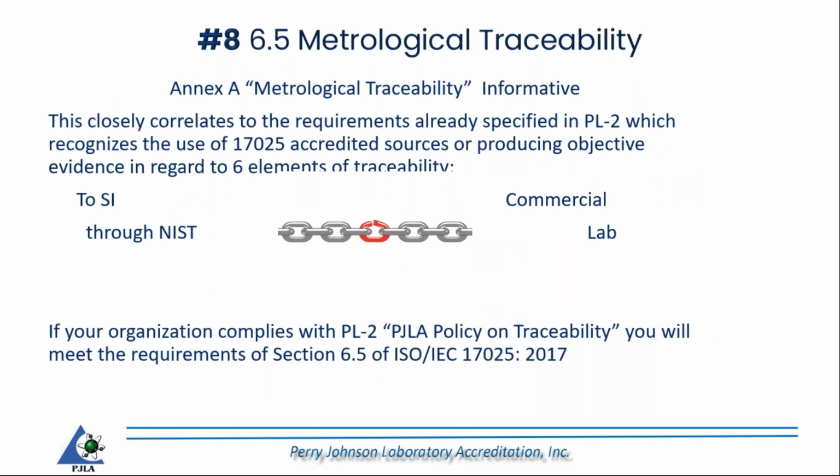Again, Annex A in the back of the standards is informative. It very closely correlates to the requirements that we have in PL2. If you're complying with PL2, our policies on traceability, you're going to be complying with 17025 requirements in Section 6.5 for metrological traceability. So, in PL2, and also the annex in back of the standard, it goes into some other detail.